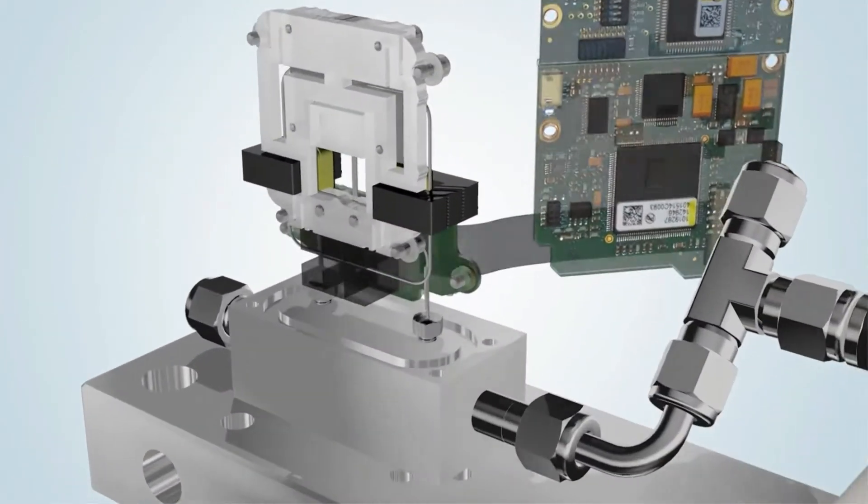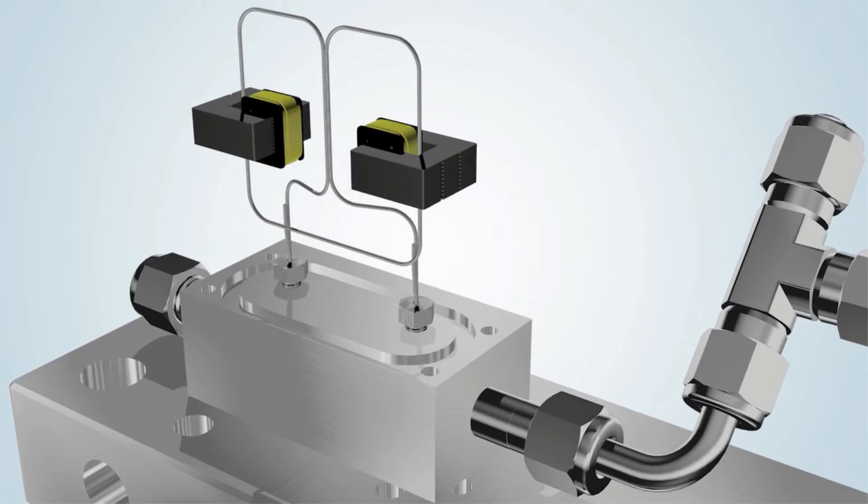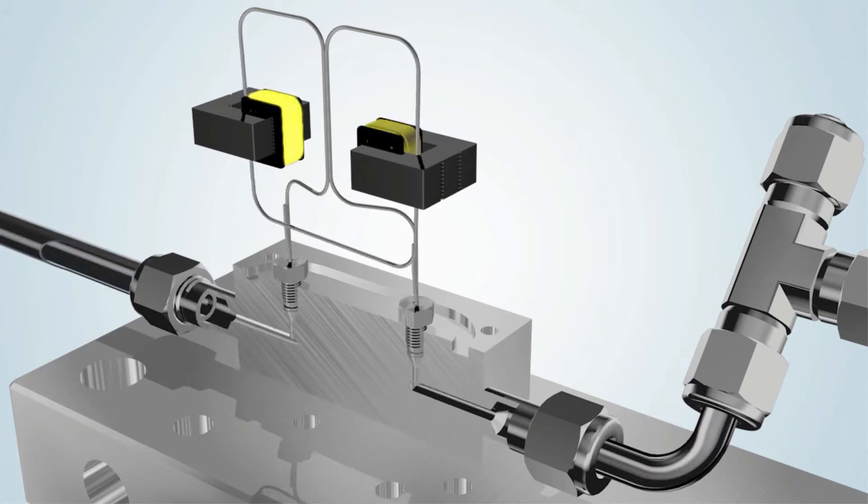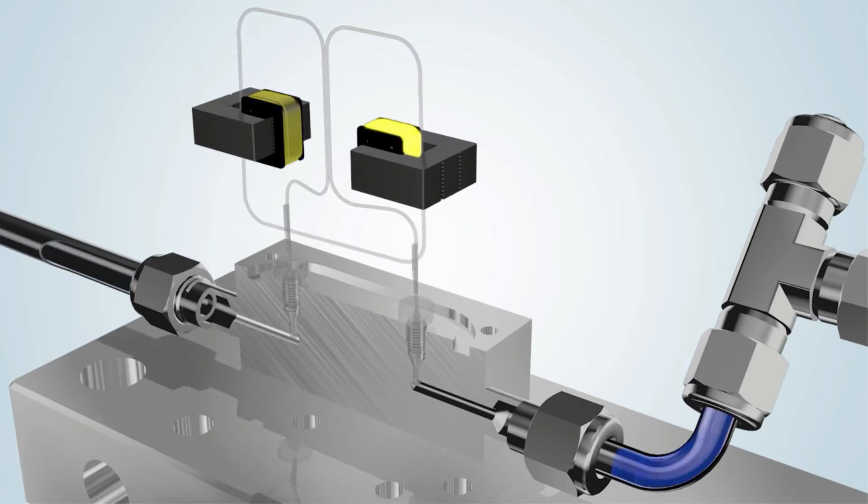This vibration, which has been slowed down considerably in the video, is generated by energizing two actuators alternately, thereby creating a magnetic field. The vibrational frequency of the tube varies depending on the instrument type, but is in the region of 370 Hertz.